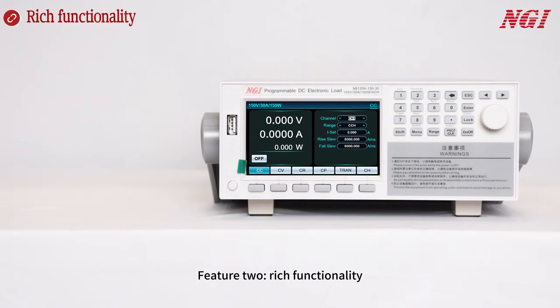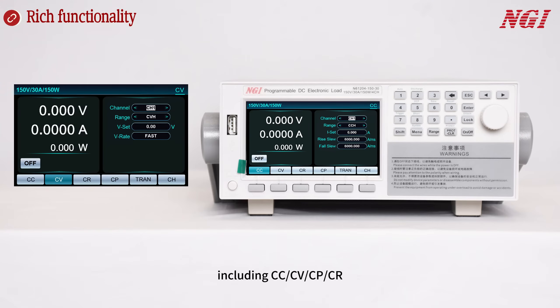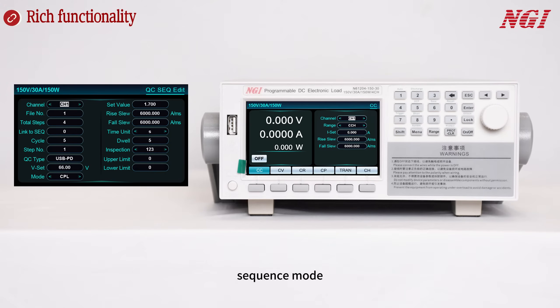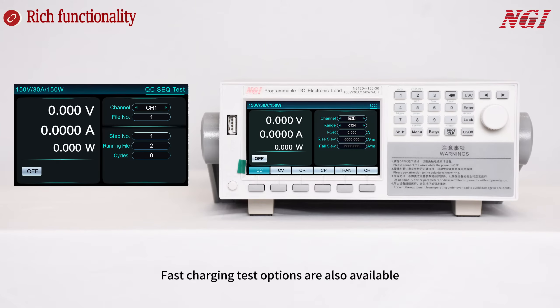Feature 2: Rich Functionality. Channels can be paralleled to expand power and support multiple modes, including CC, CV, CP, CR, CVCC, CVCR, CRCC, CPCC, Sequence Mode, LED Simulation, and OCP Test. Fast charging test options are also available.